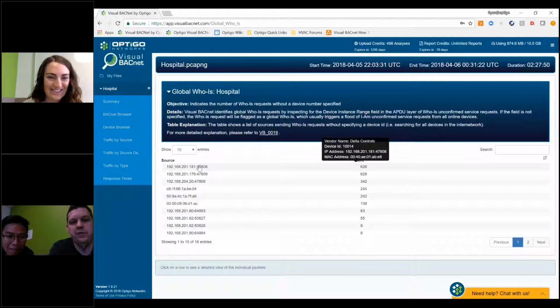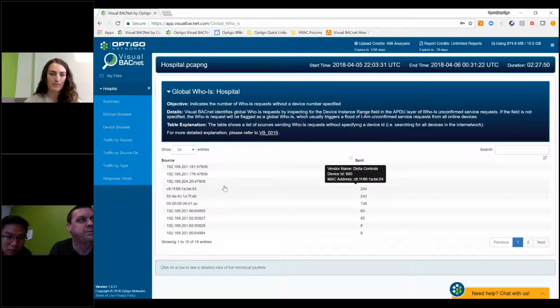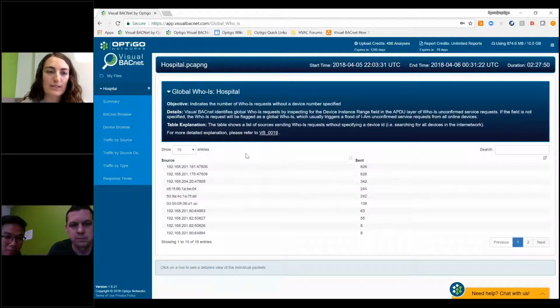Do you have any old V3 systems out there? Like the OrcaView? Do you have any OrcaView systems? Yeah, there's about a dozen OrcaView workstations on the network, and that's probably one of them. Right. So if you say there's a dozen, we're showing 18 here, so that's 12 OrcaViews, 2 IntelliWeb servers, a couple of Copper Cubes. It's pretty much your list, right? Yeah. So the fact that the top 2 are sending 626 in 2.5 hours is a lot of traffic to be on your system. Yeah.